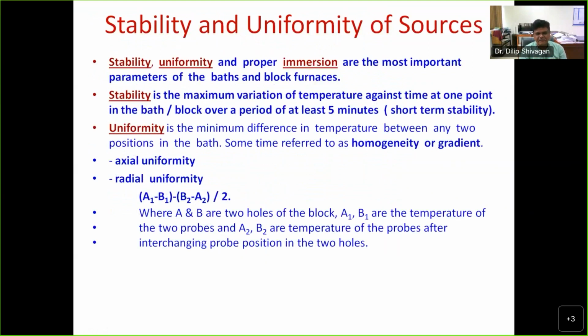You put it at one point and measure for about 1 hour, so that will give a stability. But in many cases the lengths of the thermometers are not equal. In that case, NABL and all other standard bodies also advise them to have the axial uniformity and radial uniformity. If they are loading many thermometers, then radial uniformity is also very important. One which is on the side corners or some place may not be in thermal equilibrium with the reference.